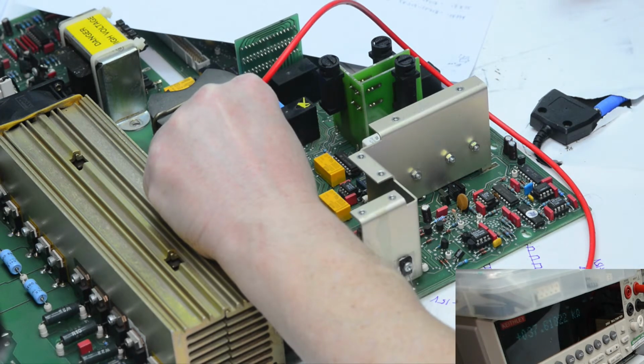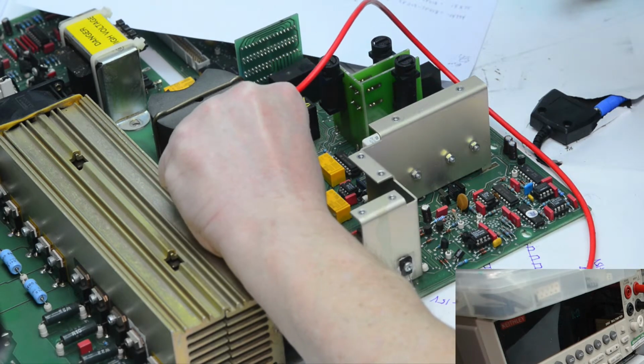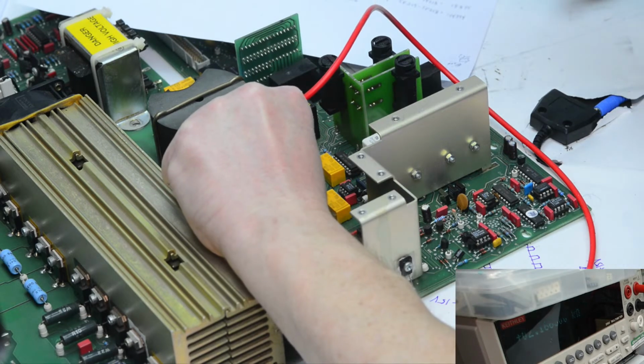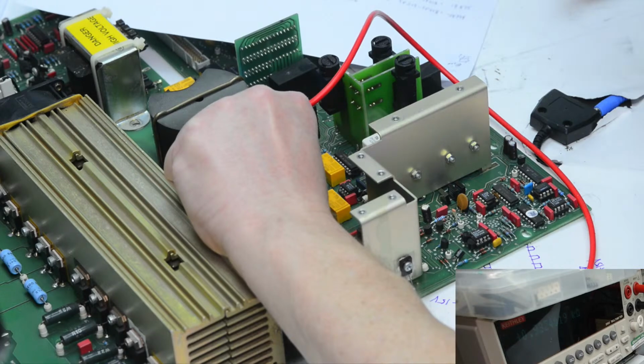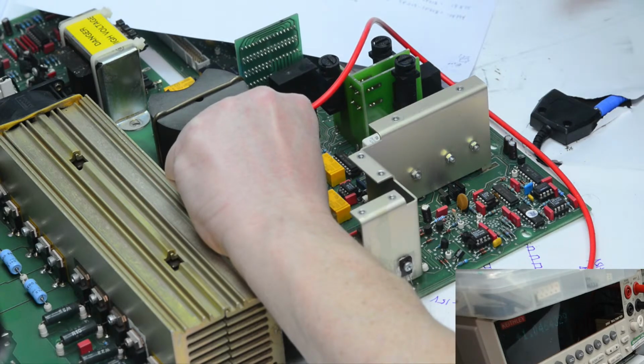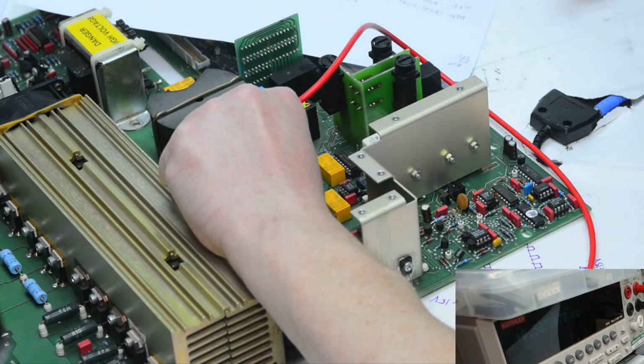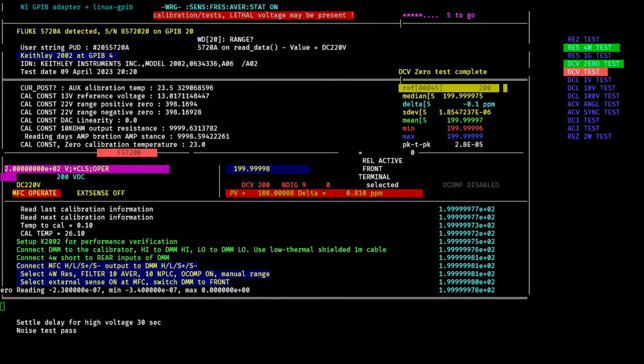Well, I was hoping that would cover some shadows. So while we're doing all that, in the background we have a 200 volt measurement on the Keithley 2002, and it's minus 0.1 ppm from the expected 200. So pretty good. That's as found on mine. No, this is the just adjusted Keithley 2002.